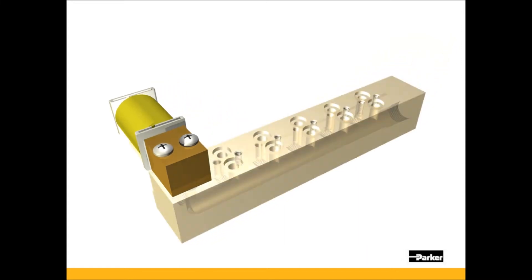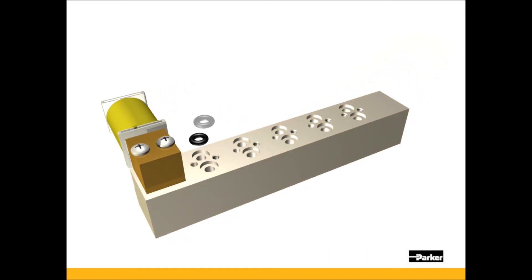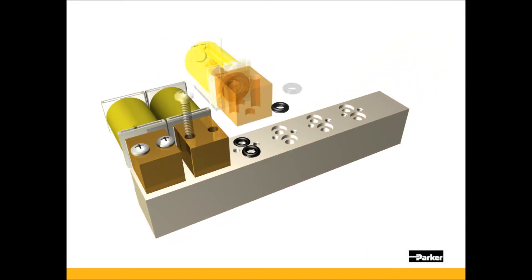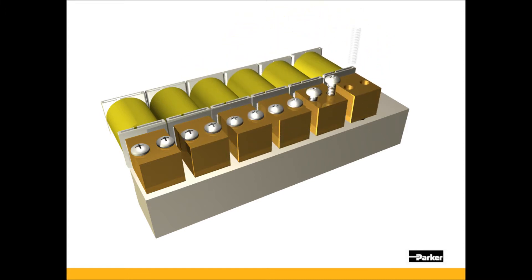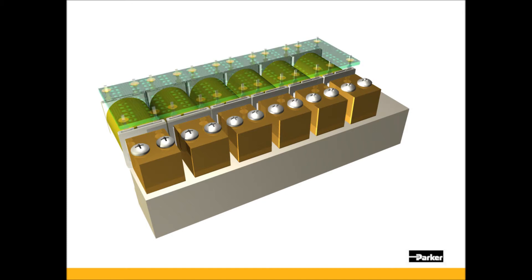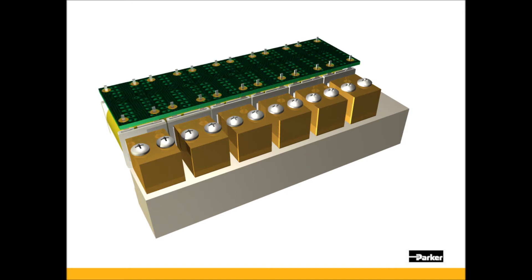When installing multiple Series 11 valves onto a manifold, two screws are required to mount each valve. Once the valves have been mechanically fastened to the manifold, a common electrical connection can be made using the 4PC pin option or by combining leads and headers.